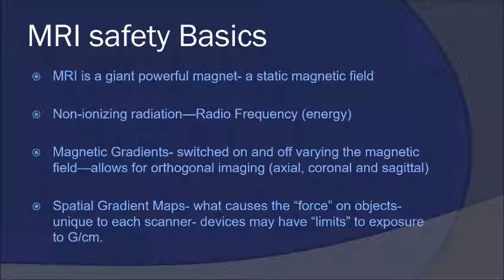There are also the parts of the magnet that make noise. These gradients, which allow for orthogonal imaging, or the ability to image in multiple planes, meaning top to bottom or axial imaging, front to back, which is coronal imaging, or side to side, which is sagittal imaging. These create a lot of noise by being switched on and off. In some of the more powerful systems, those gradient noises can exceed 120 decibels for some scanning sequences. The use of proper hearing protection is a must to minimize the potential of acoustic noise damage or hearing damage.